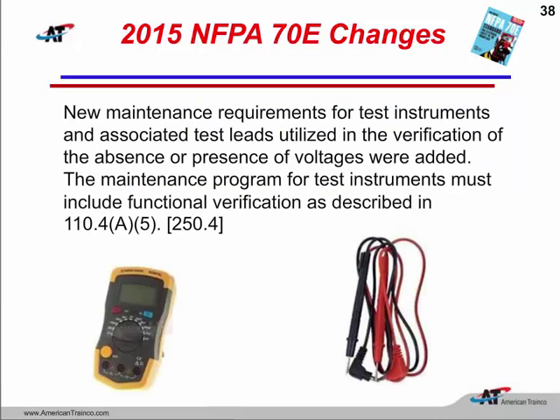New maintenance requirements for our meters. So our test leads, we're going to have to make sure this is in our electrical safety program. We're going to have to document that our meters have been calibrated, that they've been given a test, that they actually do work in all of their functions, and that the leads have also been verified that they've been maintained properly according to the manufacturer.